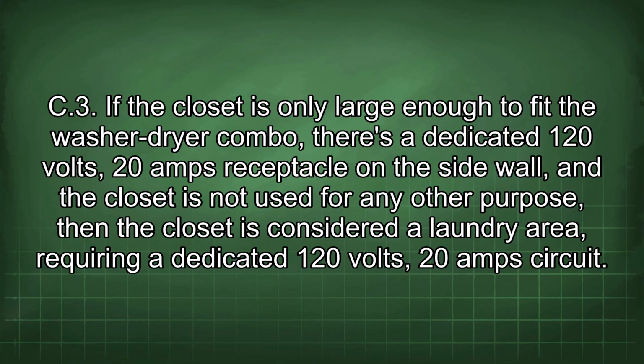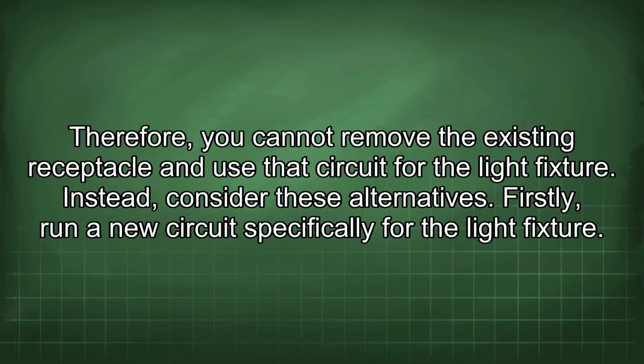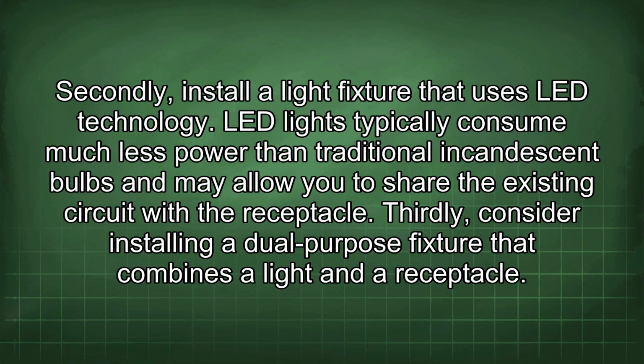receptacle on the side wall, and the closet is not used for any other purpose, then the closet is considered a laundry area, requiring a dedicated 120 volts, 20 amp circuit. Therefore, you cannot remove the existing receptacle and use that circuit for the light fixture. Instead, consider these alternatives. Firstly, run a new circuit specifically for the light fixture. Secondly, install a light fixture that uses LED technology.